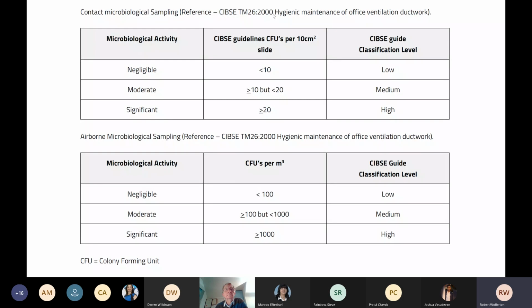So here we've got guidance. We wouldn't generally recommend using bacterial tests on an internal ductwork system for a verification of cleanliness, because generally they will usually fail. We've had circumstances where we've actually disinfected the ductwork prior to taking a test to do a blank test, and we've had those come back and fail.